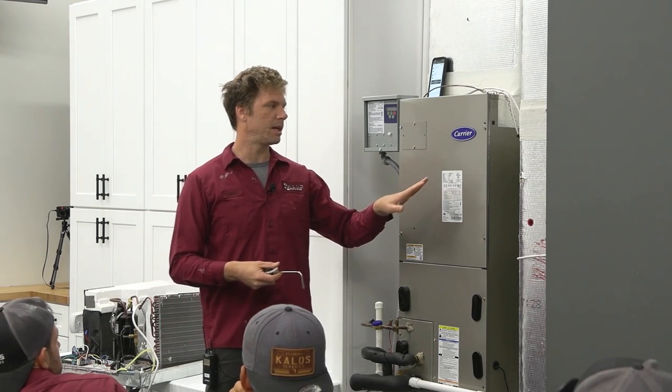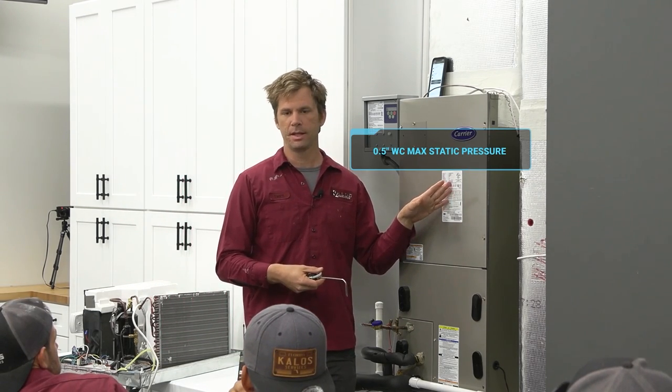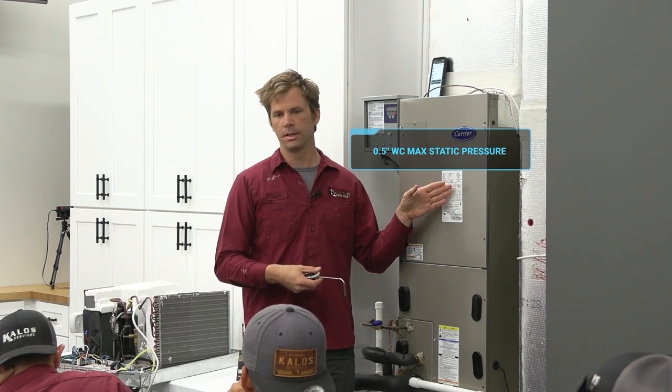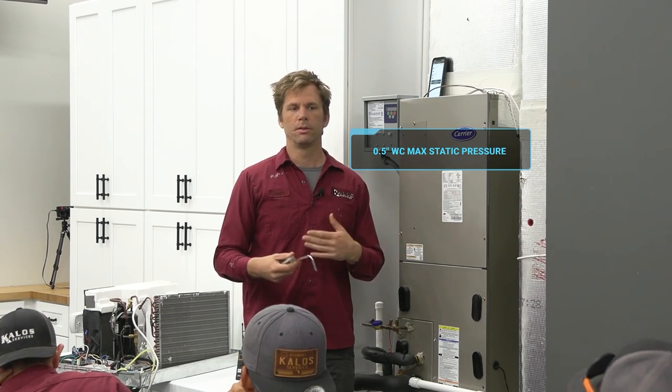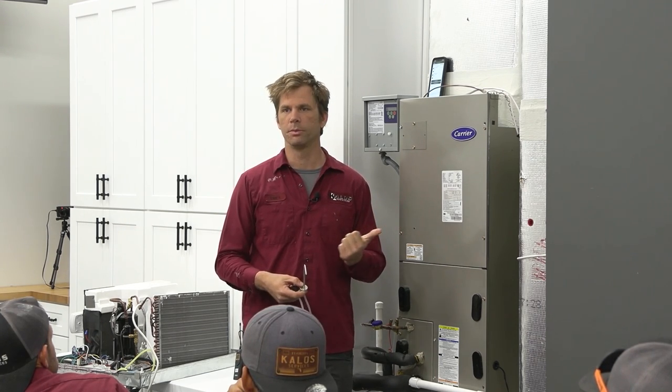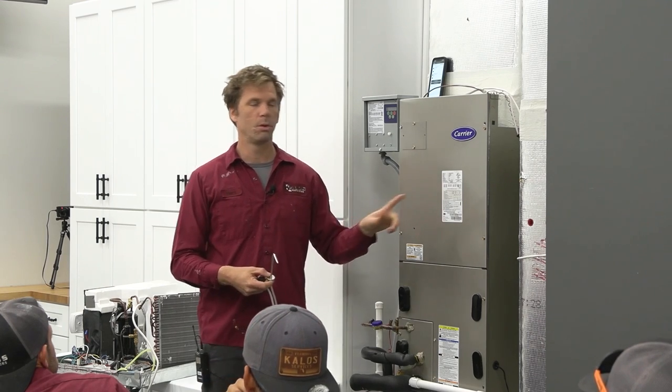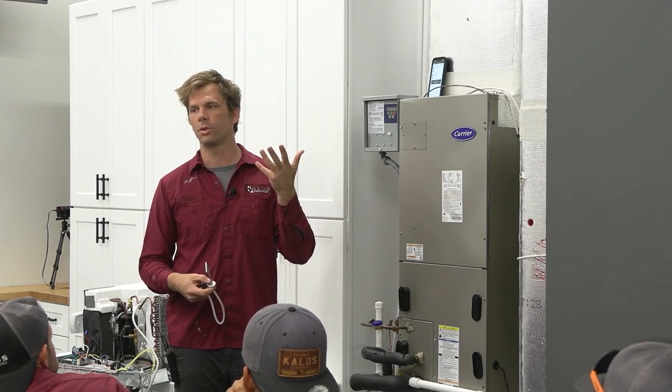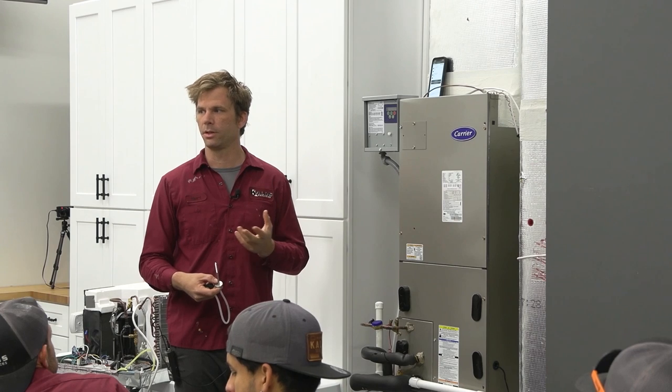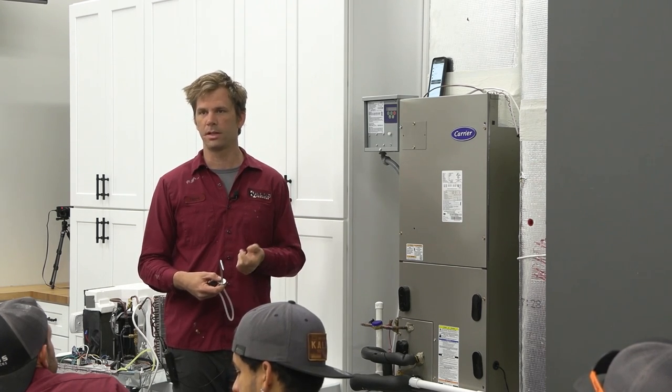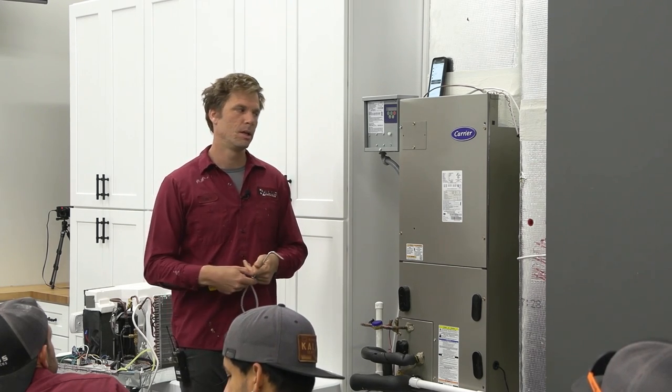The system is designed for 0.5 as its max static pressure. Real life application, you can get above that. Once you start getting above 0.8, close to one inch of static pressure, you're going to start burning through blower motors. You're really cutting down your CFM. Your blower motor ramps up to try to overcome that resistance, so you're pulling a lot higher amps. Not as efficient as the system.